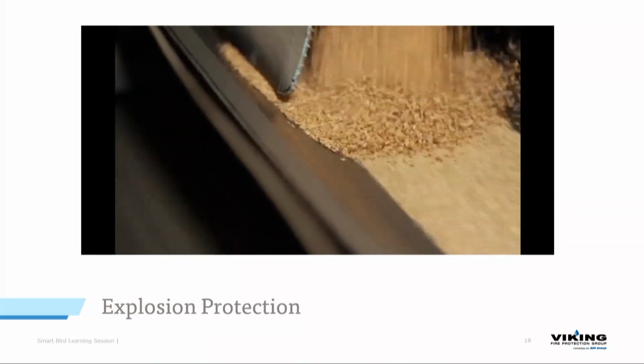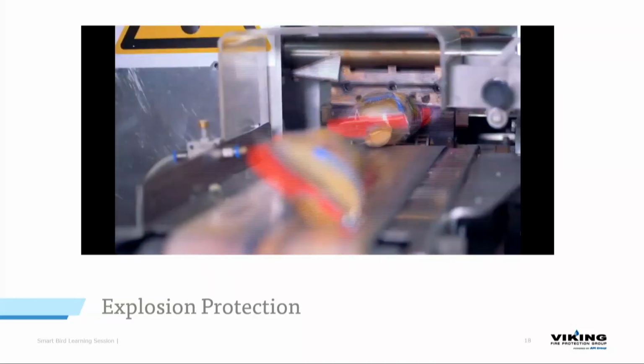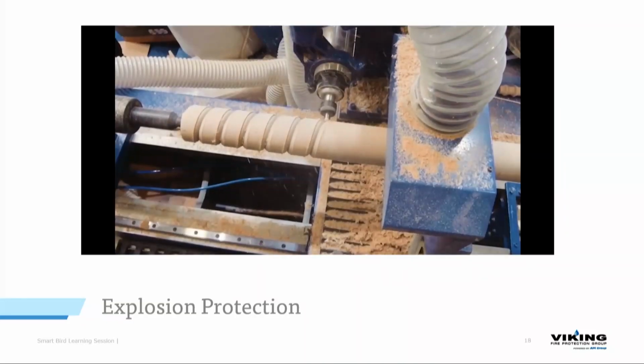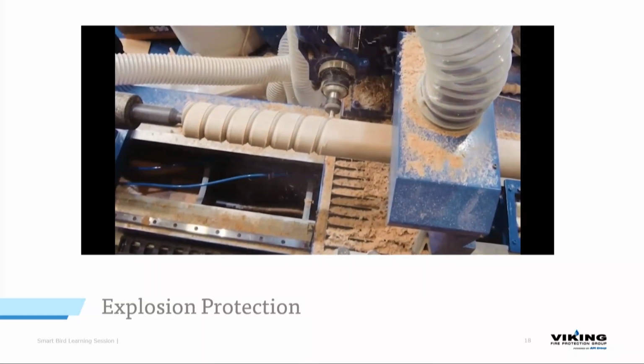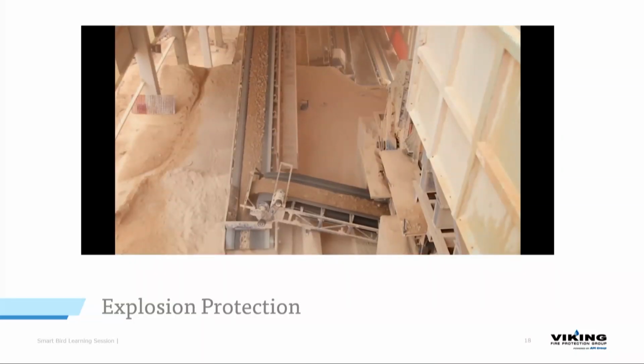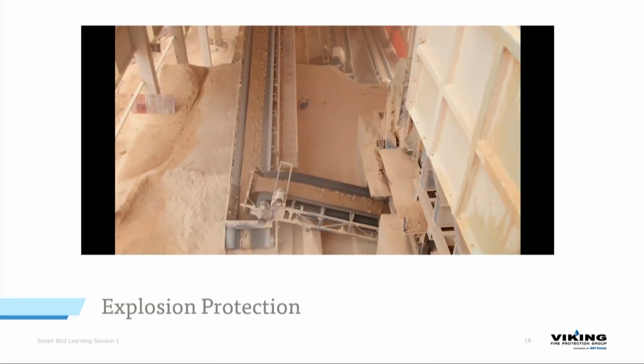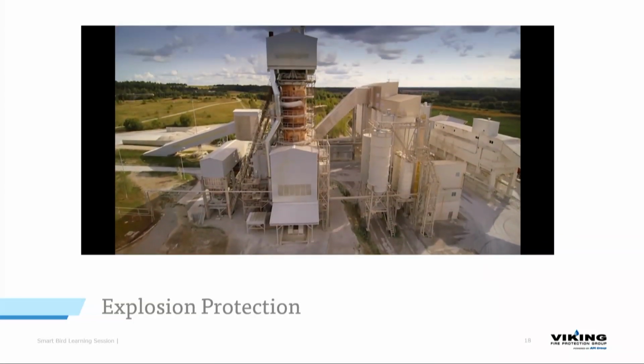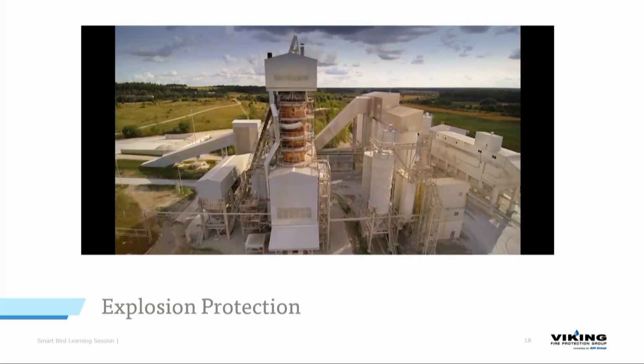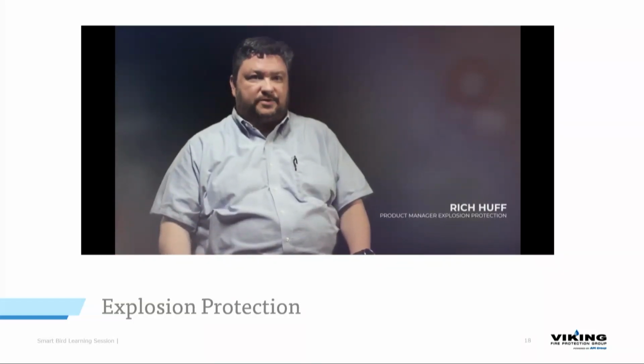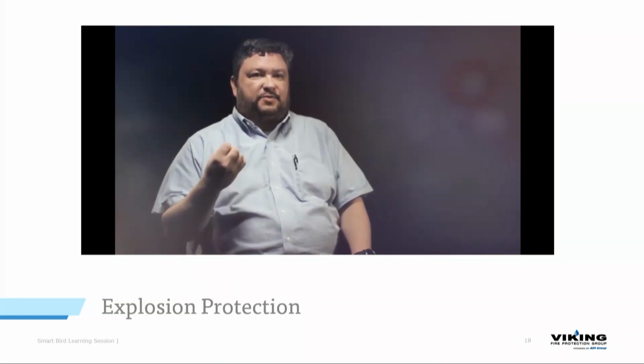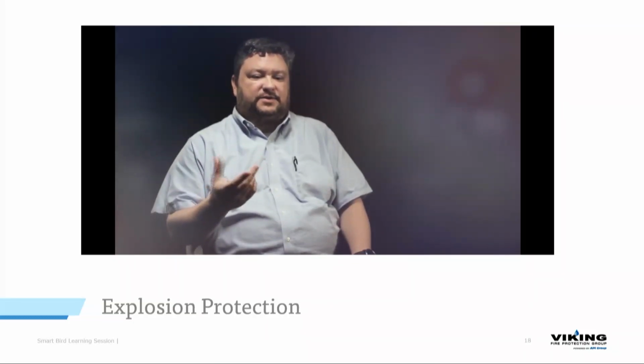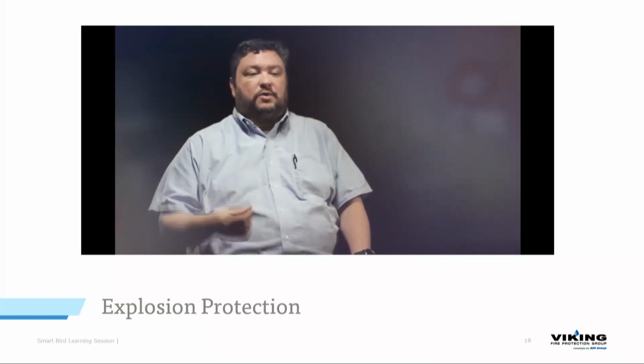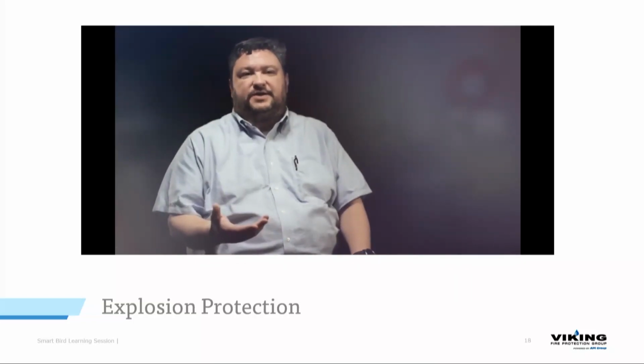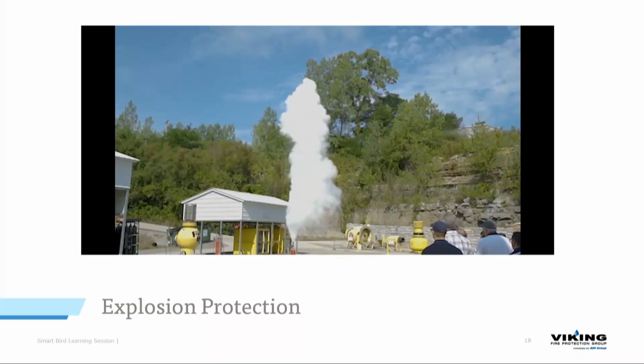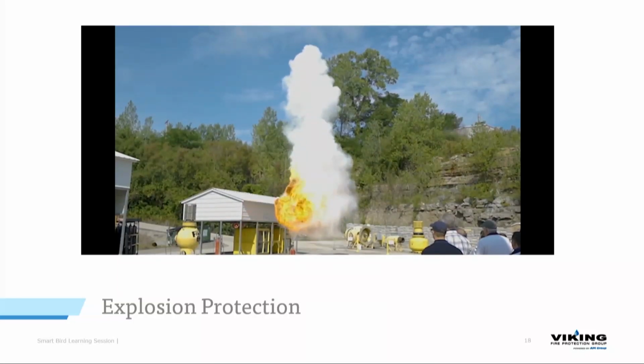Combustible dust can be a problem in a lot of different industries. Food and beverage industry, pharmaceuticals, chemical, and many others, a lot of wood processing. Any carbon-based dust, and sometimes even plastics and metals, if they're in dust form, they're susceptible to explosions. Explosion suppression systems have to be very fast in order to do their job. From the time an explosion starts, and a tiny spark or whatever the ignition source is will light the suspended fuel, that suspended dust in the air. There will be a fireball that starts to grow and the pressure wave coming out of it as well.